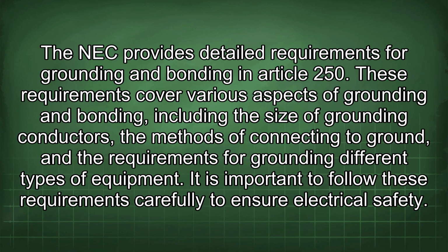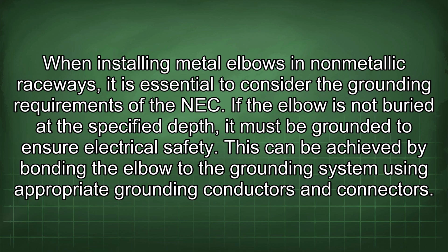The NEC provides detailed requirements for grounding and bonding in Article 250. These requirements cover various aspects of grounding and bonding, including the size of grounding conductors, the methods of connecting to ground, and the requirements for grounding different types of equipment. It is important to follow these requirements carefully to ensure electrical safety. When installing metal elbows in non-metallic raceways, it is essential to consider the grounding requirements of the NEC. If the elbow is not buried at the specified depth, it must be grounded to ensure electrical safety. This can be achieved by bonding the elbow to the grounding system using appropriate grounding conductors and connectors.